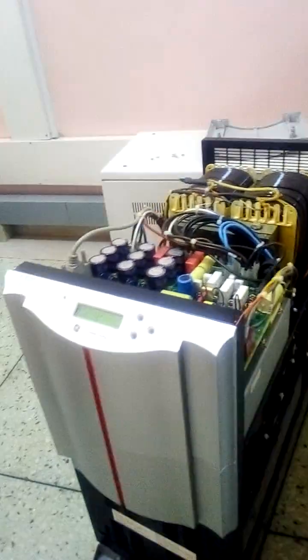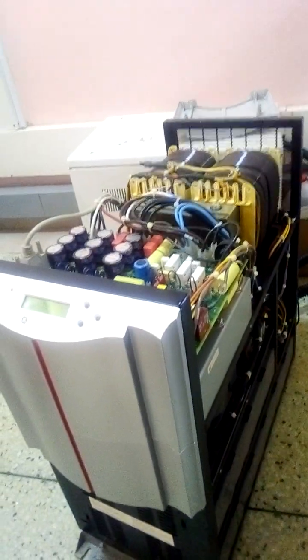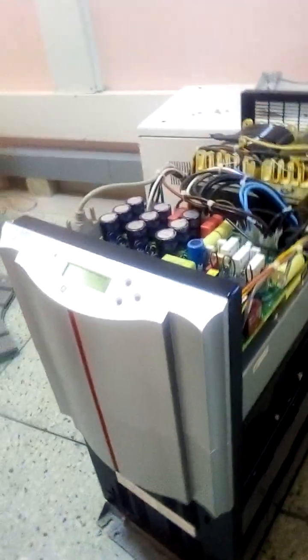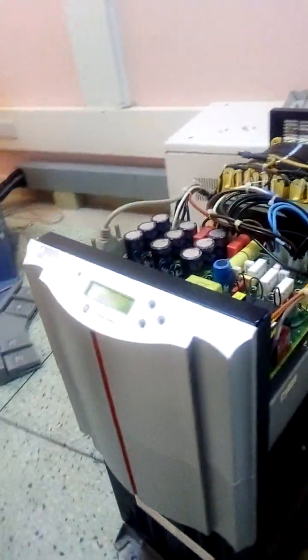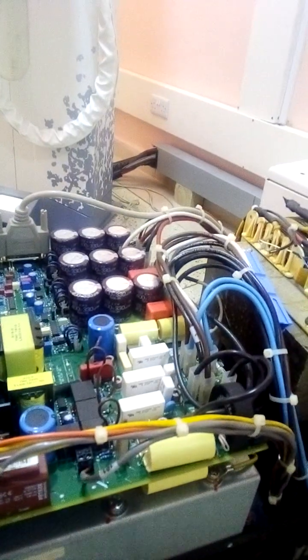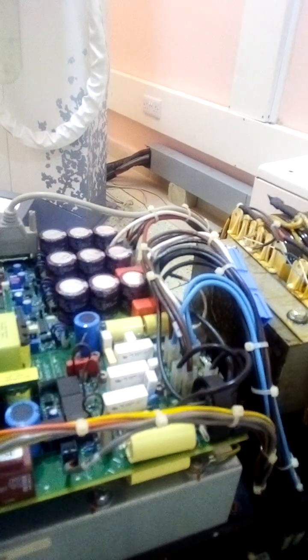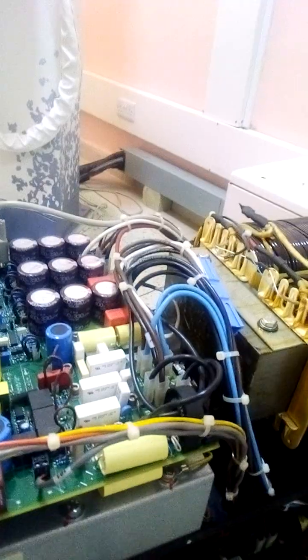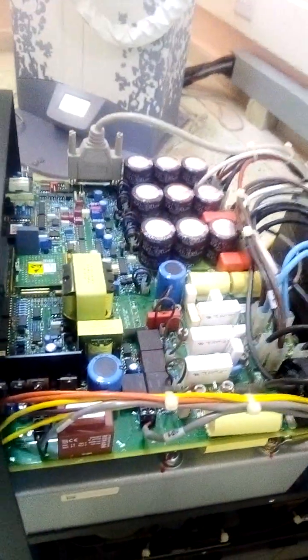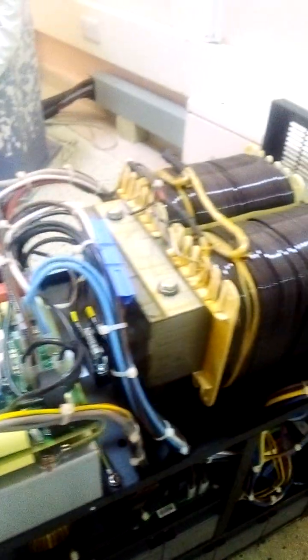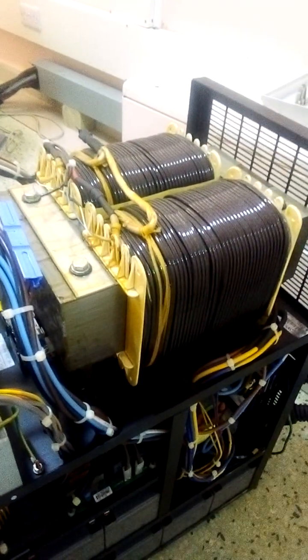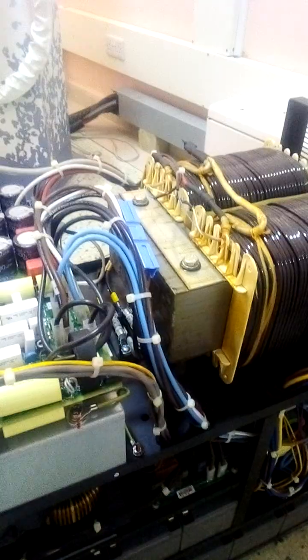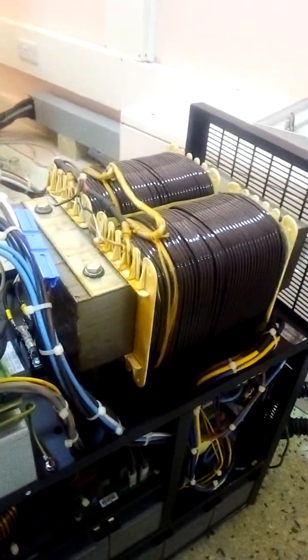power backup. Once the main power fails, this UPS will be responsible for converting 24 volts from the batteries that are installed down here to 240 volts power, which is quite enough to run the system. And you can see we have an inverter up here for the UPS, and we have the transformer which converts 24 volts to 240 volts.